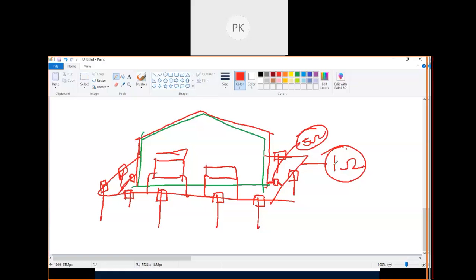Now let's say I have a transformer somewhere here, feeding power to this through a cable trench. Now this trench also needs to have an earthing conductor in it. Then I will have an earth grid around this transformer.